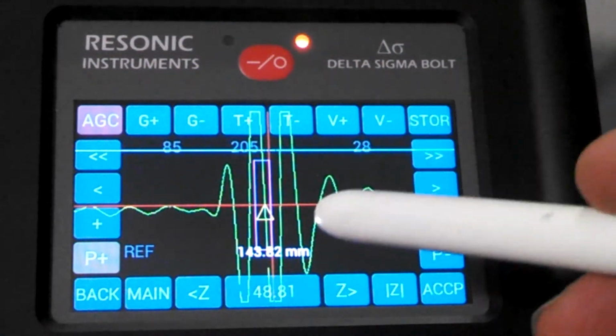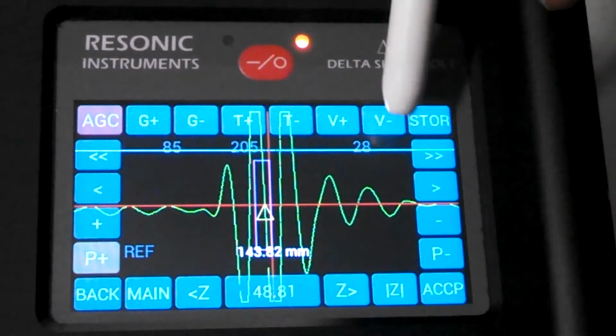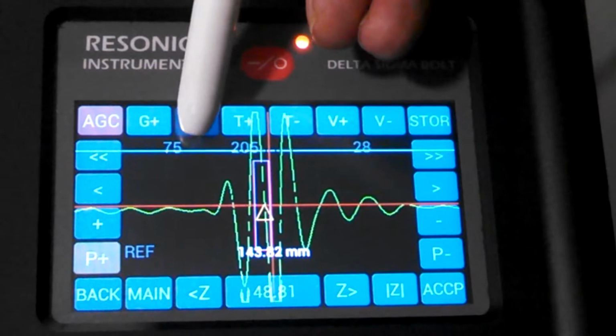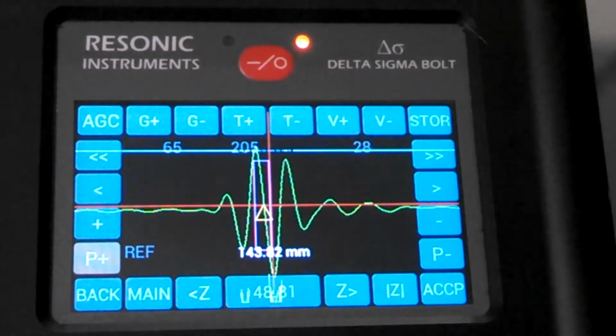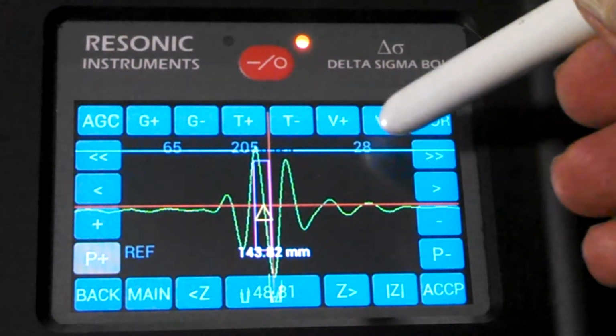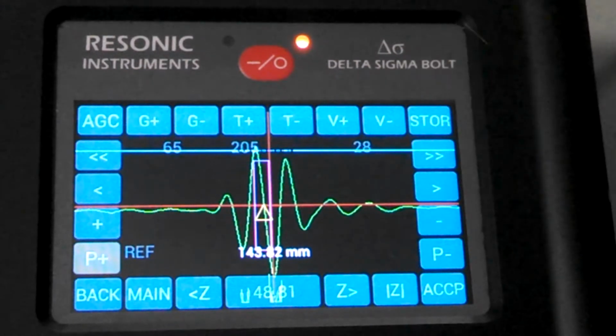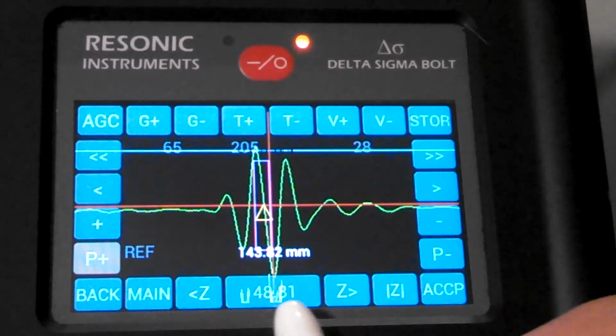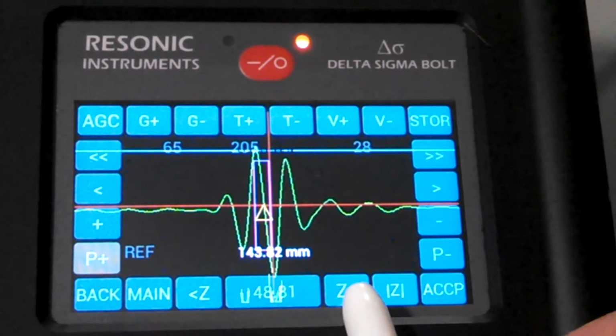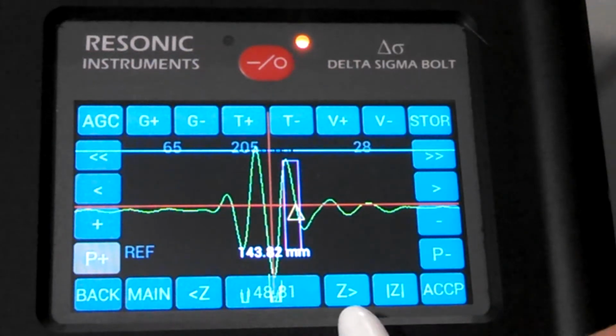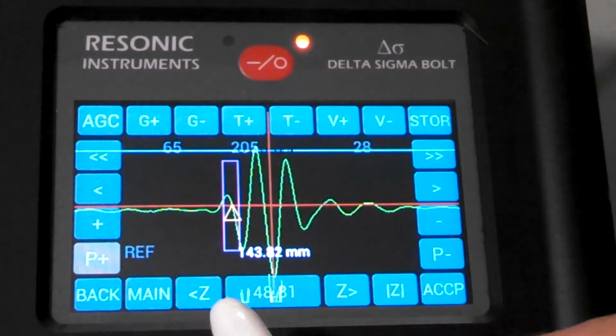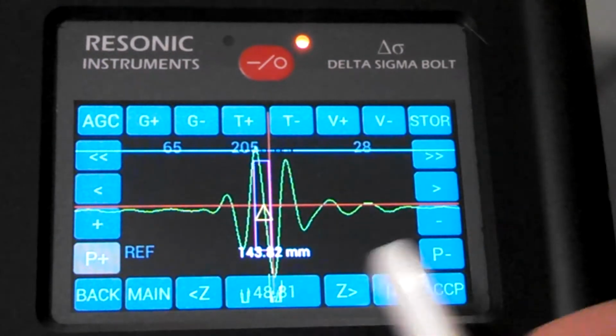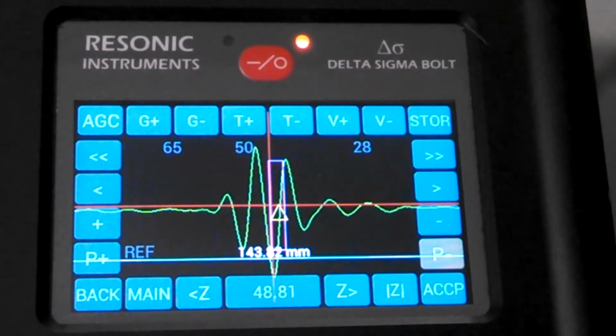We're back to 143. I can bring the gain down. Bringing the voltage up has the same effect as bringing the gain down. We bring the gain down. With the DS1, operating at the smaller amount of voltage on the pulser is the best way to go because it takes less power and creates less noise. The Z right caret moves the blue box zero crossing anywhere on the signal. If you want to change the zero crossing on that polarity, of course we can always do it on the reference length. You can change the polarity.